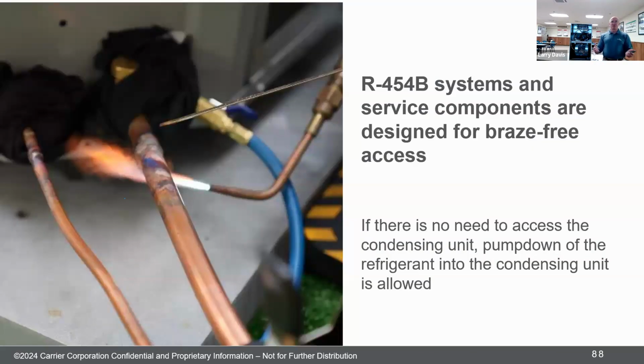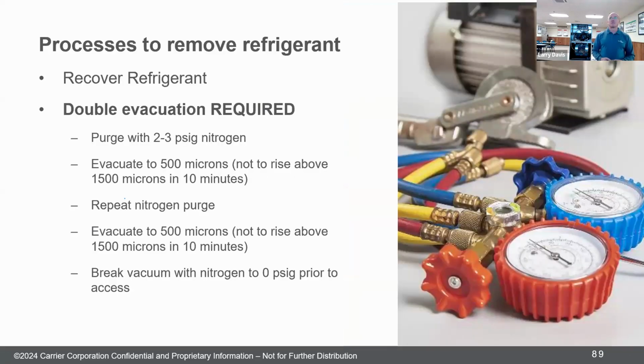If you're servicing a 454B system and you have to fix something on the indoor coil or line set, and you don't have to access the condensing unit or anything in there, you can still pump it down and isolate it through the valves. Okay. All right, here's the process.